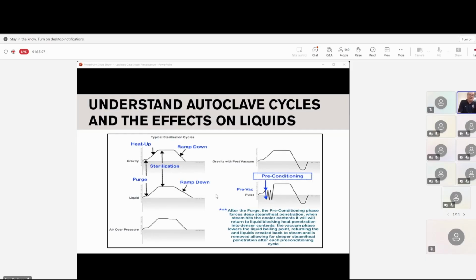Now on the gravity and liquid, you see that they're very much the same, except for the ramp down at the end. And I'll explain that. So you go through the purge, you see that little hump in the beginning. There's a little bit of a purge, and your purge is very, very critical to an autoclave. What the purge does is it takes either 1 minute to 3 minutes. I generally run, the ones that I controlled, I put a 3-minute purge in it. When you open the autoclave and you shut it, you're going to get little air pockets in the chamber. You have to get rid of those. And what happens is, if you can see, they will shrink, and it's like a balloon of air. And as it gets heat and pressure, it won't heat up. So there are pockets within that could harbor a virus or a spore that'll never achieve the temperature.